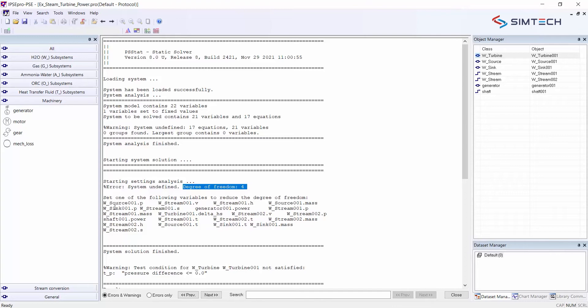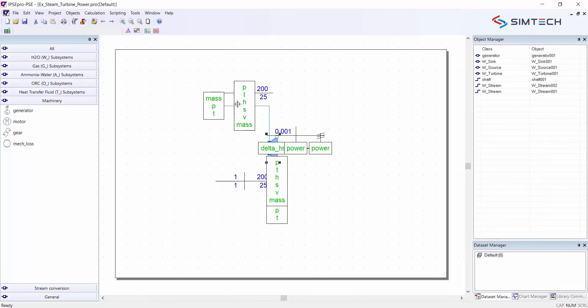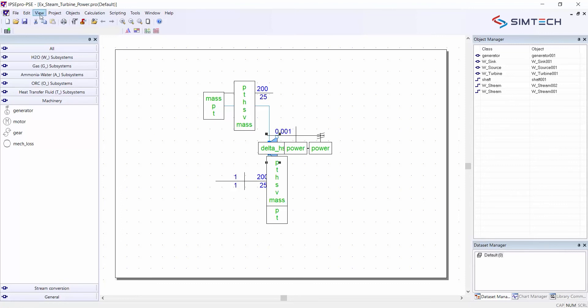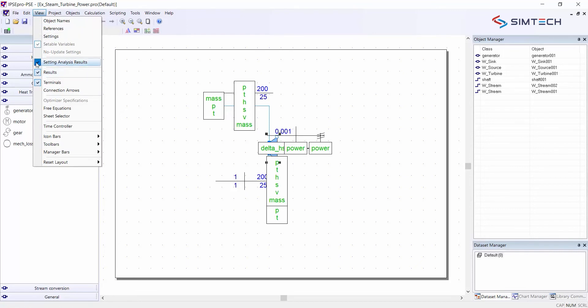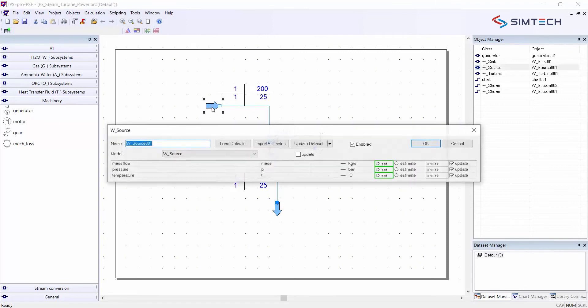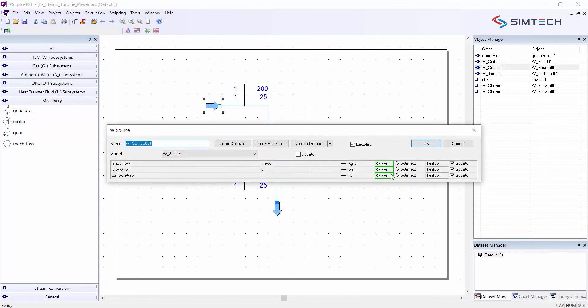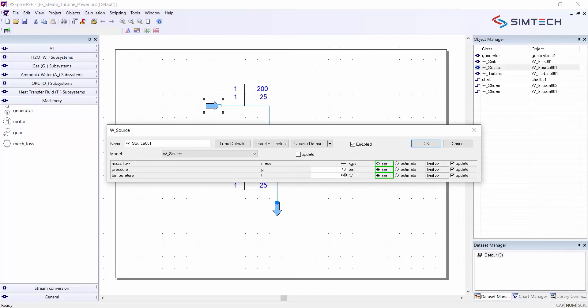So the system cannot be fully solved but a few more variables have to be set. I can choose from these variables. Here it is written in text but on the screen the settings analysis shows me instantly which variables I can set. And here it is quite obvious I will first choose my live steam conditions to set them. So I remove the settings analysis results and double click here on the source. And here for live steam conditions I set pressure of 40 bars and 440 degrees Celsius.